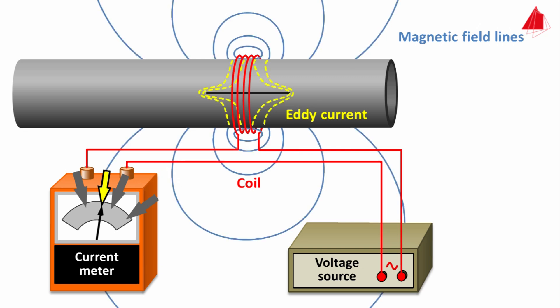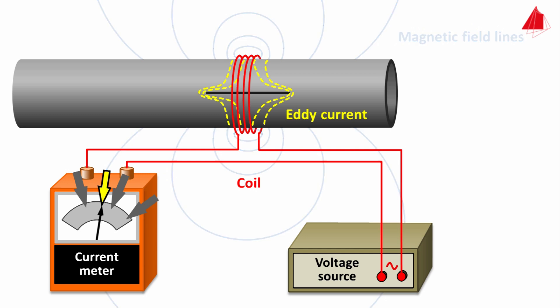In practice, the alternating current frequencies are not as low as shown here for demonstration — they are much higher, typically in the region of some kilohertz. From now on we're going to omit the magnetic field lines in the animation and represent the eddy current in a simplified static way. In eddy current testing with coaxial probes, the coils are either pushed coaxially over the workpiece or pushed through the workpiece.